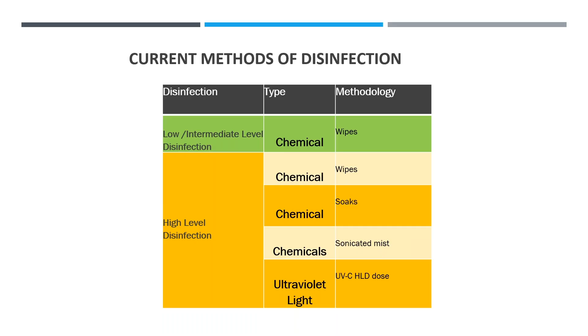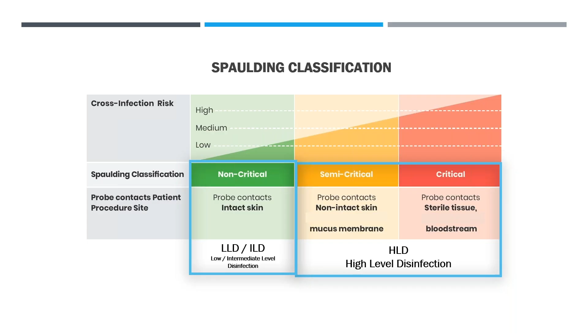And then in addition to that, we have ultraviolet light. So really, it may appear to be complicated at first, but the clinician has only one decision to make, and that is, if you are putting a probe over clean, intact skin that doesn't become contaminated with body fluid, then low-level disinfection or intermediate-level disinfection is appropriate. In all other situations, high-level disinfection is what is required. So it becomes a binary decision.